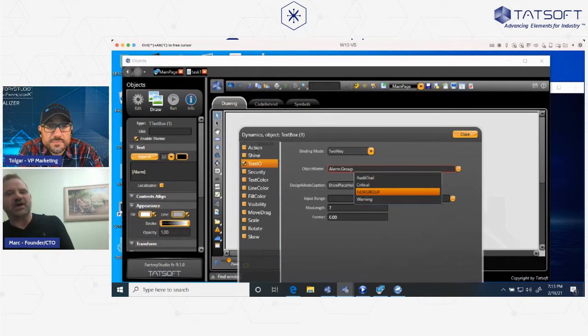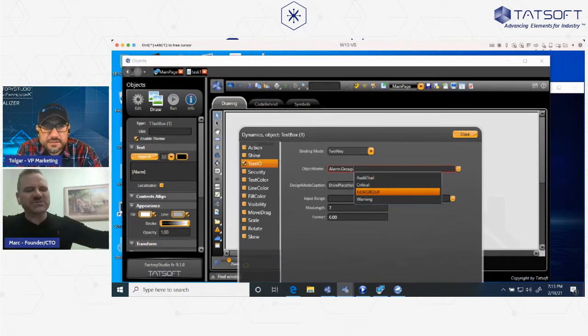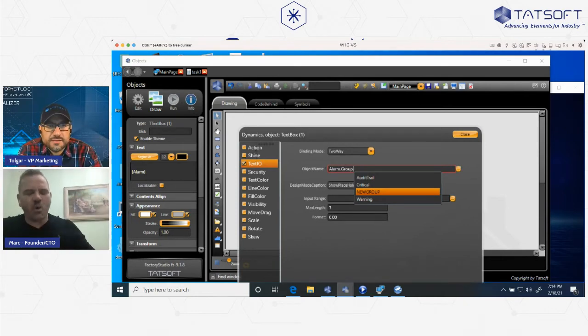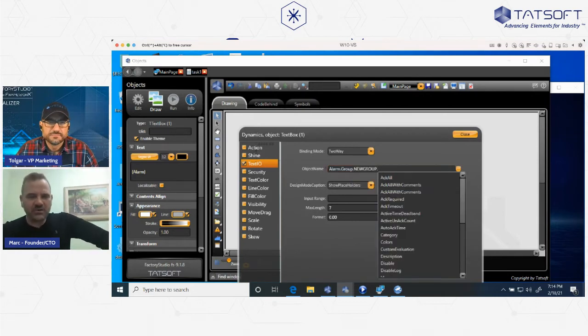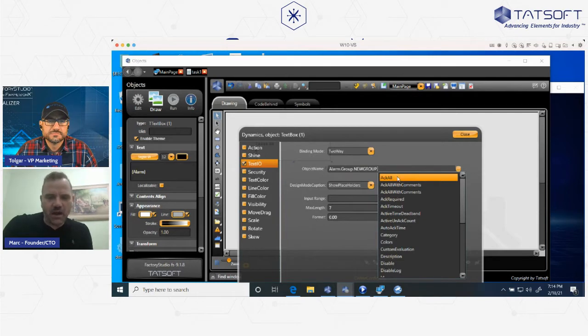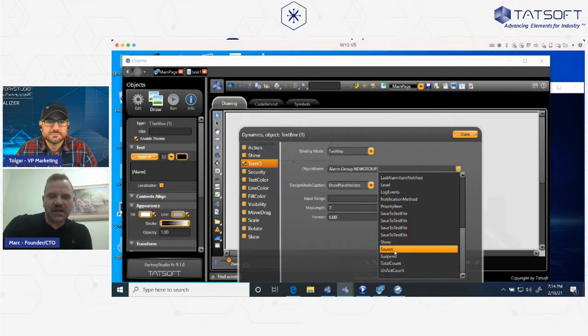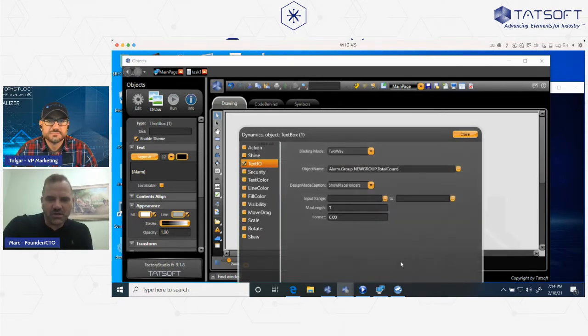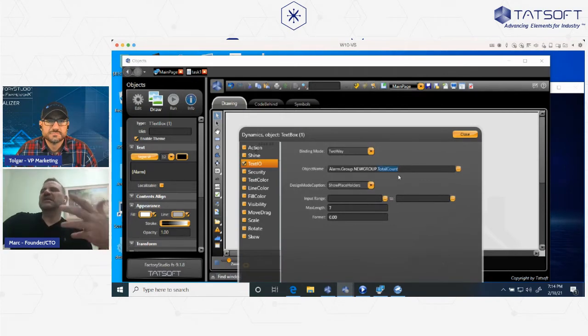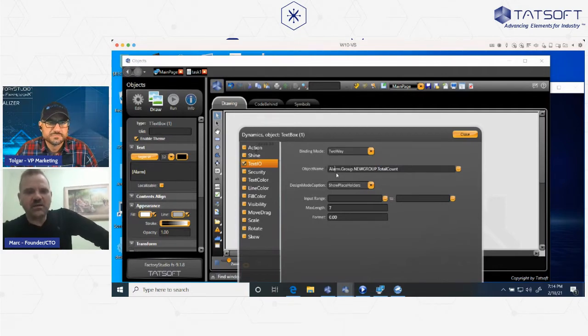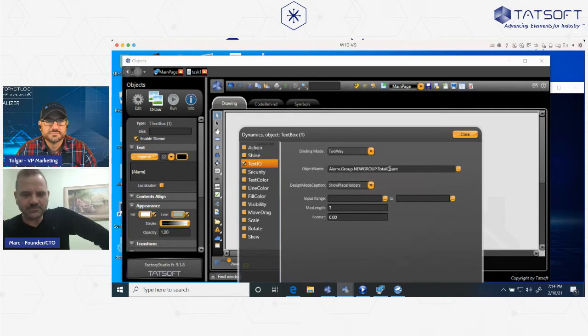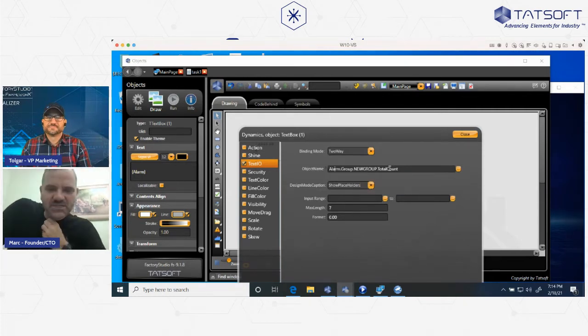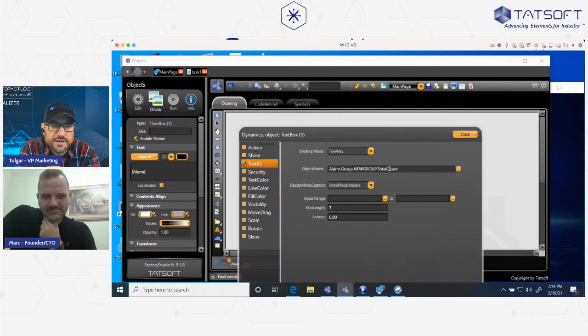The new group I created is already showing because all modifications go to the project database configuration online and are accessible right away — no need to save. So if I go to this new group and see what I can do: I can acknowledge all alarms, I can have the total count of alarms, search color. For instance, the property 'TotalCount' — you don't even need to know programming. If you're an automation engineer and you see 'Alarm Group New Group TotalCount,' you understand the meaning immediately.